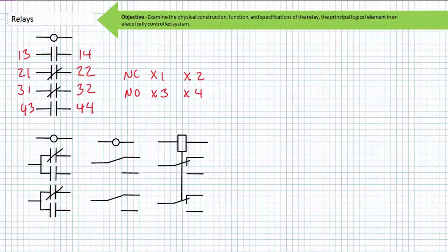IceCube relays with single-pole double-throw switches use a similar numbering scheme. The first digit is assigned the number of that particular switch. This is the first switch associated with this relay, so each terminal's first digit would be 1. The common terminal's second digit is 1.